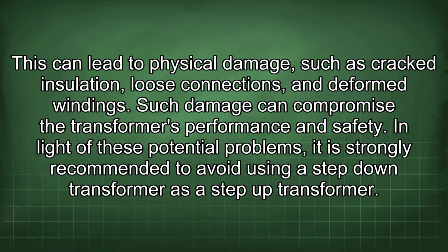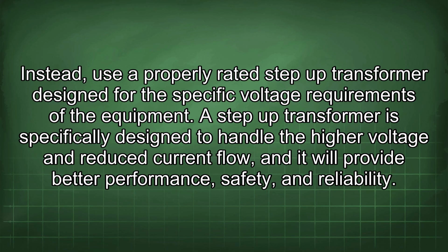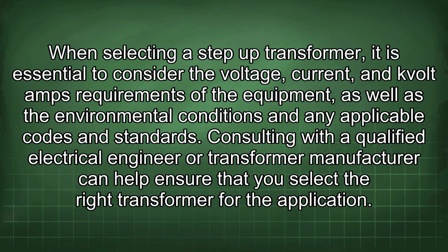In light of these potential problems, it is strongly recommended to avoid using a step-down transformer as a step-up transformer. Instead, use a properly rated step-up transformer designed for the specific voltage requirements of the equipment. A step-up transformer is specifically designed to handle the higher voltage and reduced current flow, and it will provide better performance, safety, and reliability. When selecting a step-up transformer, it is essential to consider the voltage, current, and kVA requirements of the equipment, as well as the environmental conditions and any applicable codes and standards. Consulting with a qualified electrical engineer or transformer manufacturer can help ensure that you select the right transformer for the application.